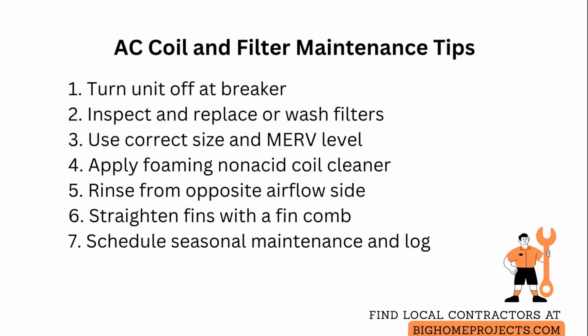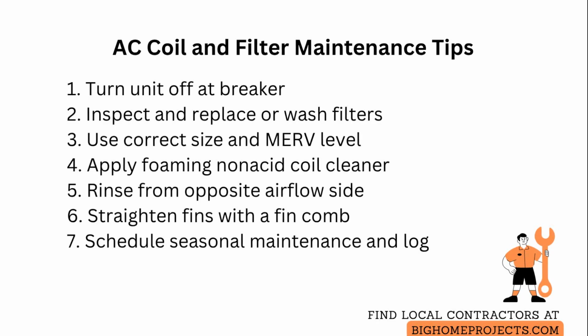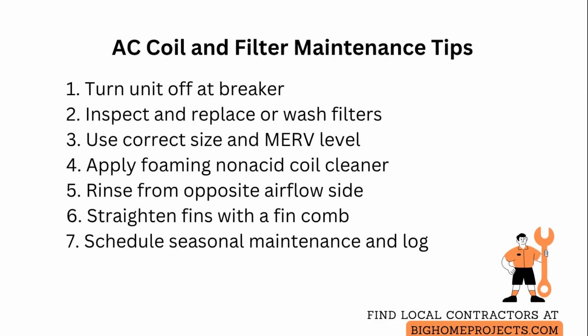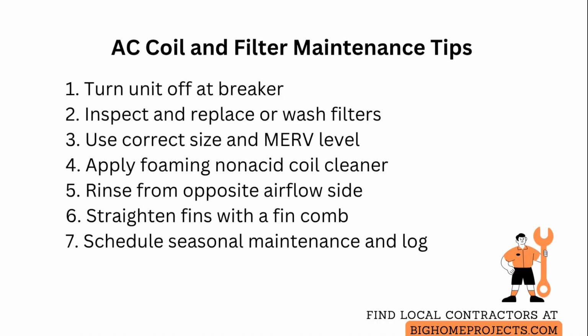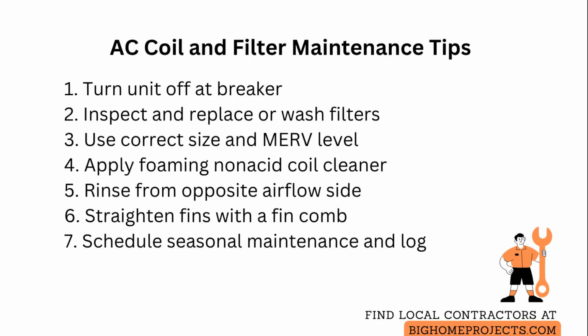For evaporator and condenser coils, use a foaming non-acid coil cleaner labeled safe for residential systems. Spray evenly across the fins and allow the foam to dissolve grime for the time the product specifies. Then rinse with low-pressure water from the opposite side of airflow to avoid bending fins. Straighten bent fins gently with a fin comb to restore airflow, and check for any oil or refrigerant stains that indicate leaks requiring a professional.